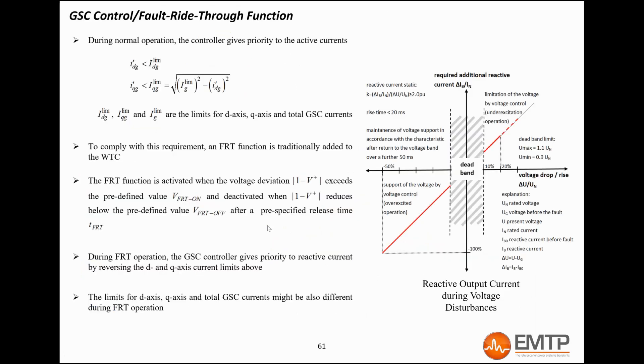Let's now explain the limiter device. During normal operation, the controller gives the priority to the active currents. The controllers are equipped with an FRT function to fulfill the grid code requirements regarding voltage support. The FRT function is activated when the grid voltage deviation is above a user-defined threshold, and is deactivated when the deviation goes back below another threshold. When the FRT function is active, the controller gives the priority to the reactive current.